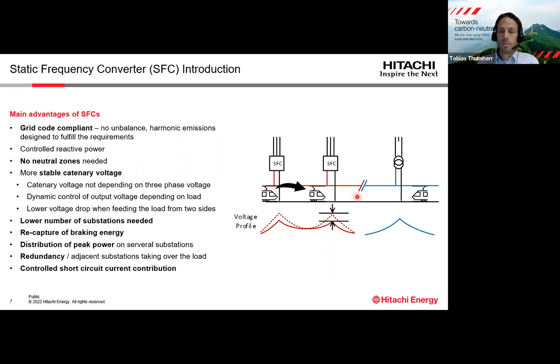And last but not least, we have a controlled short circuit current contribution from the SFC. SFCs have inherently a lower short circuit contribution than a transformer, because transformers are typically overloadable by a factor of 2 or 3 for a short time. On the other hand, the SFCs can really control how much current they contribute to a short circuit, and this is especially helpful if an SFC is used as an extension of the power supply for an existing line, and the equipment is not designed for a higher fault current. So in that case, the SFC fault current contribution can be set to a value below nominal.